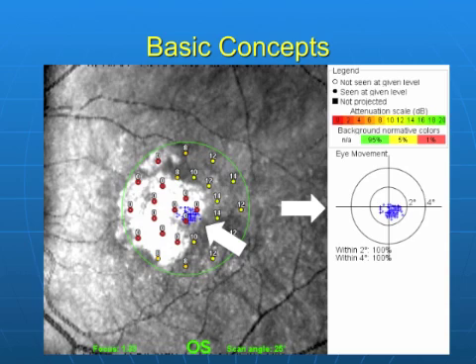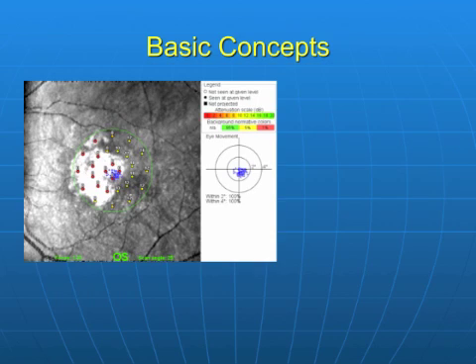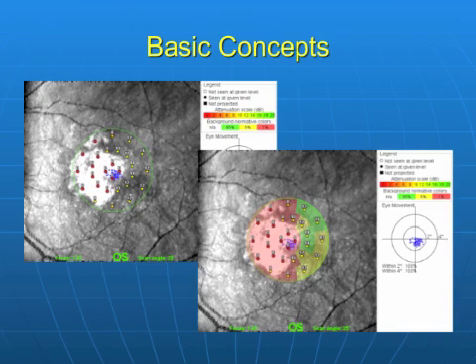Each test also produces a fixation scatter plot. Each time a stimulus is presented, a mark is made on the plot. A tight central pattern is a sign of relatively good visual function. The plot will also show you the locus of fixation on the retina. The sensitivity map can also be viewed or printed with a color-keyed decibel value overlay, which is useful for assessing the significance of the map at a glance. The hot colors represent relatively low sensitivity and the cool colors represent relatively high sensitivity.